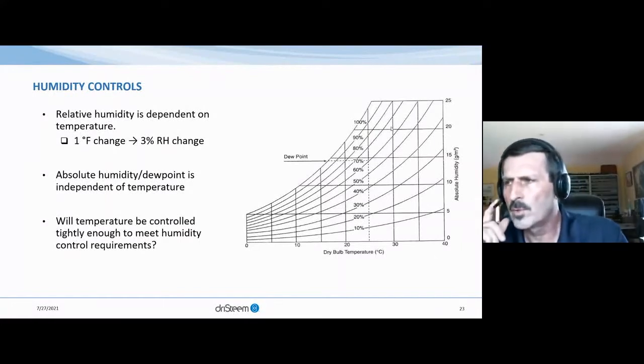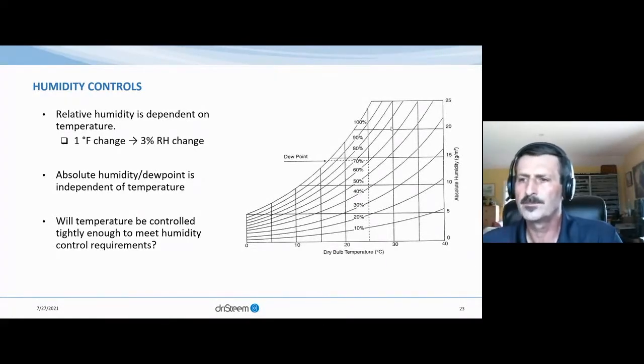A further note on controls: if we are controlling for relative humidity, we must recall that relative humidity is linked to temperature. A 1 degree Fahrenheit change in temperature will result in a 3% change in relative humidity. You can see that any attempt to maintain a high degree of accuracy and stable process conditions will also require tight temperature control from your other systems.